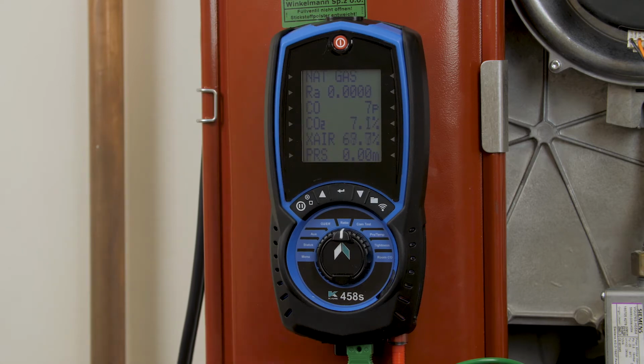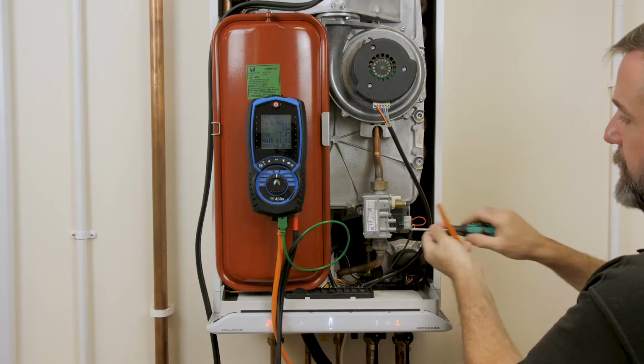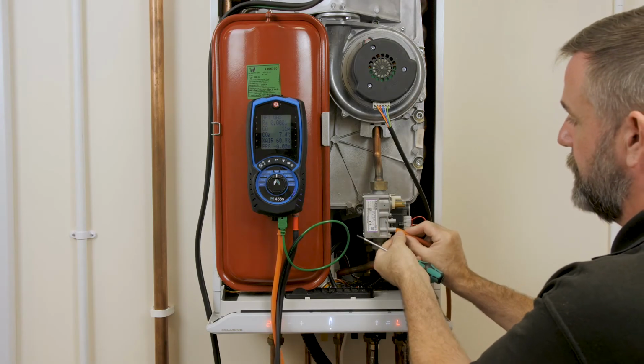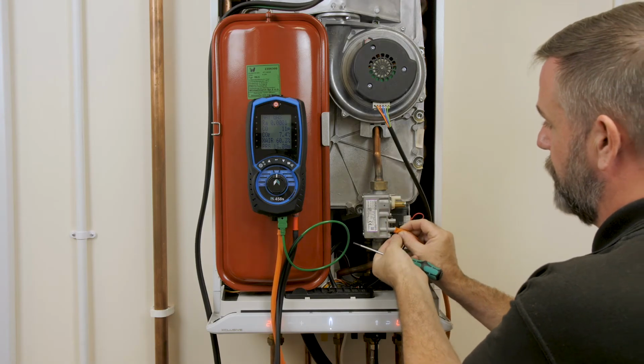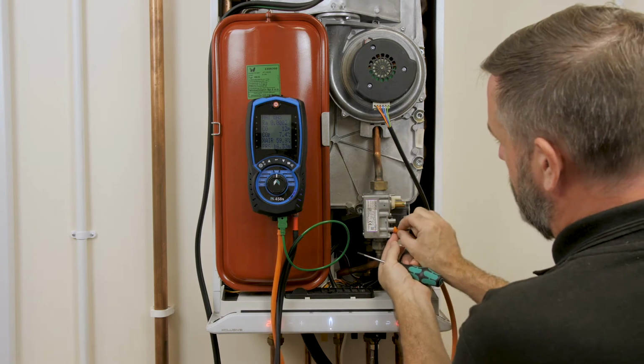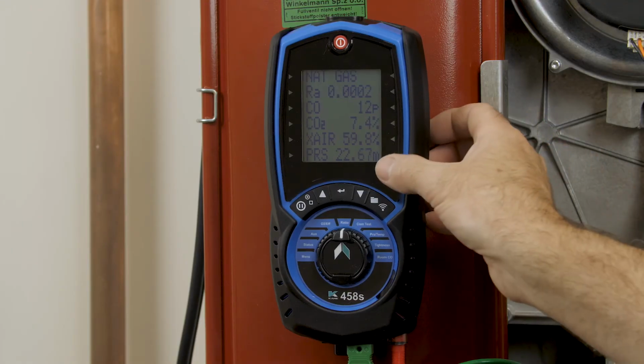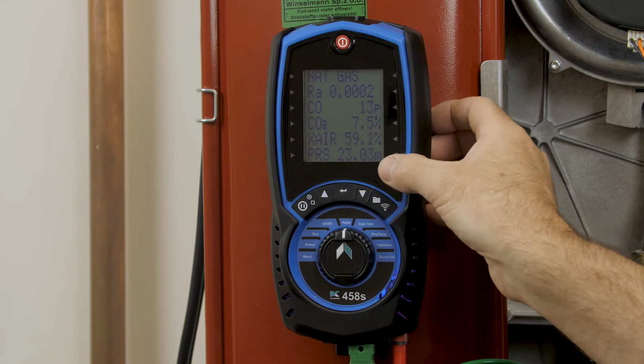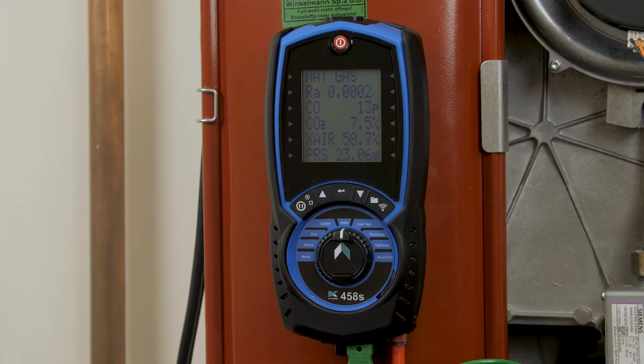We can also connect the flue gas analyzer to the sample point on your gas valve. And now we get the working pressure of the boiler in low fire.